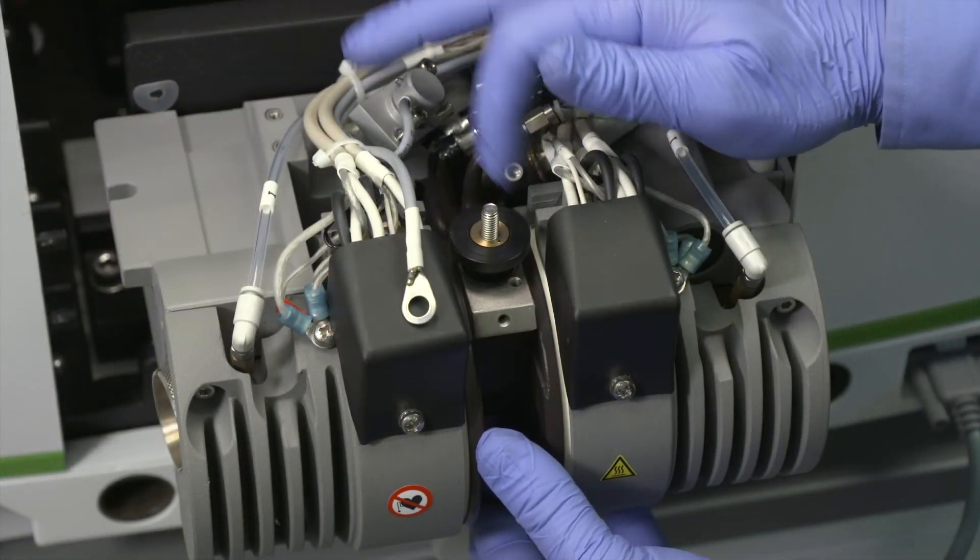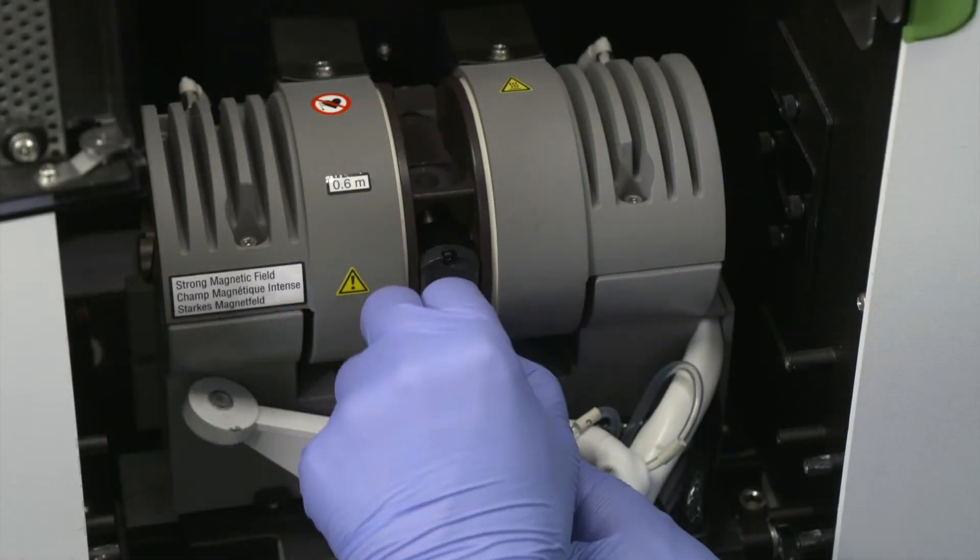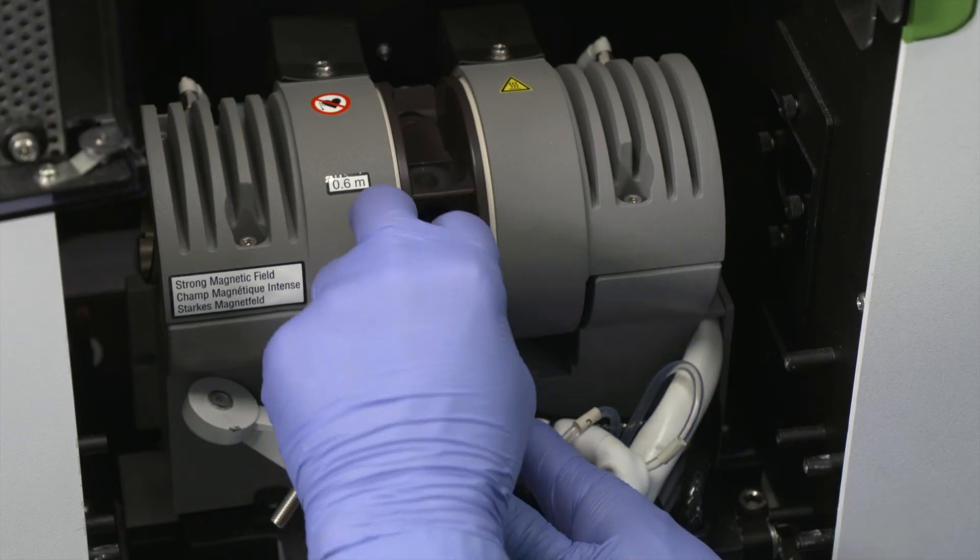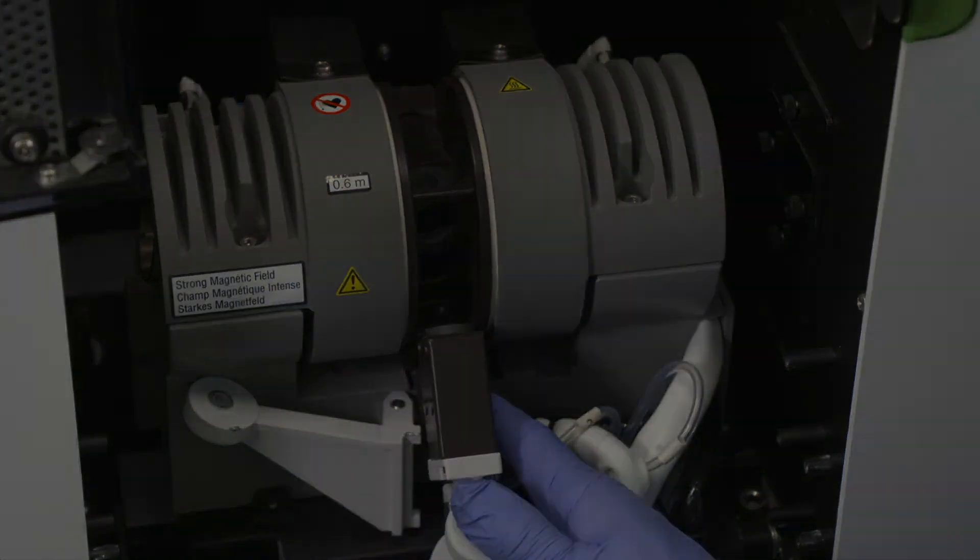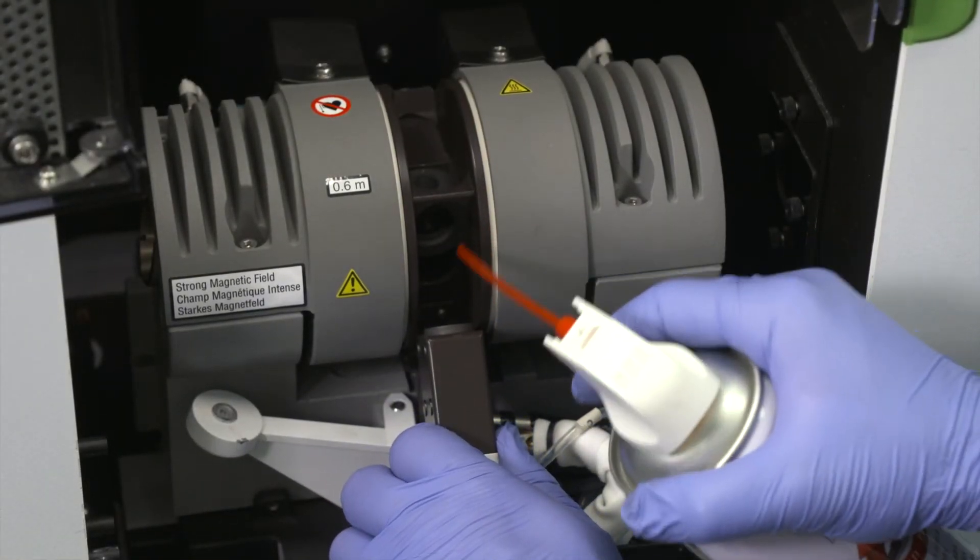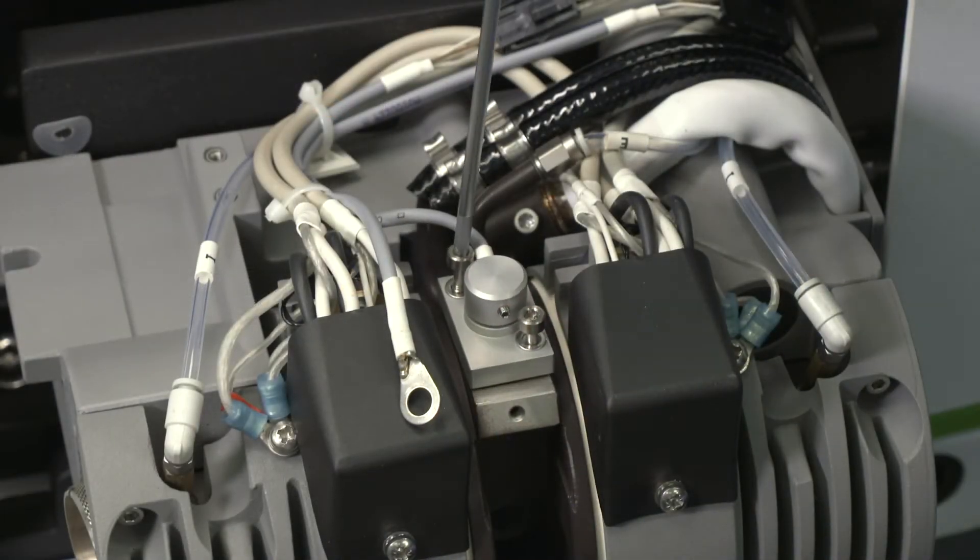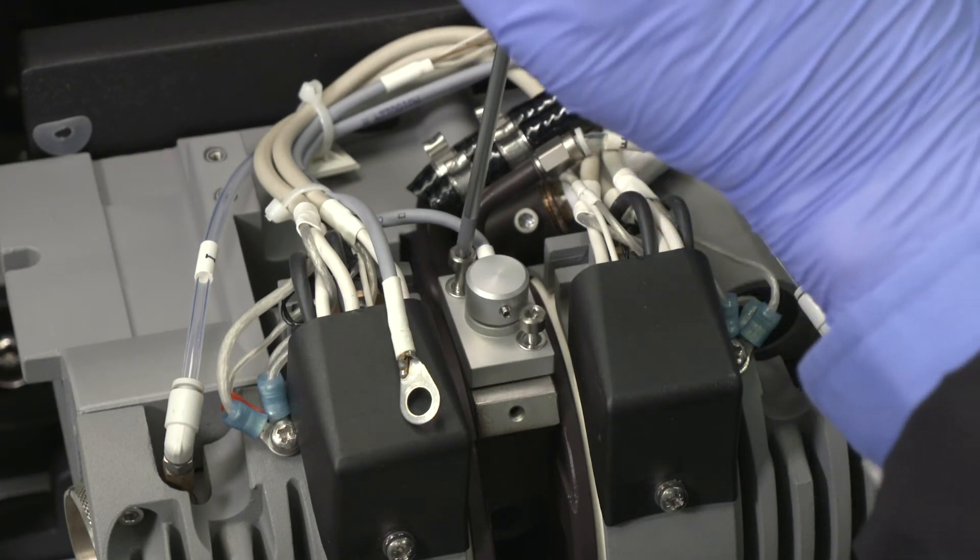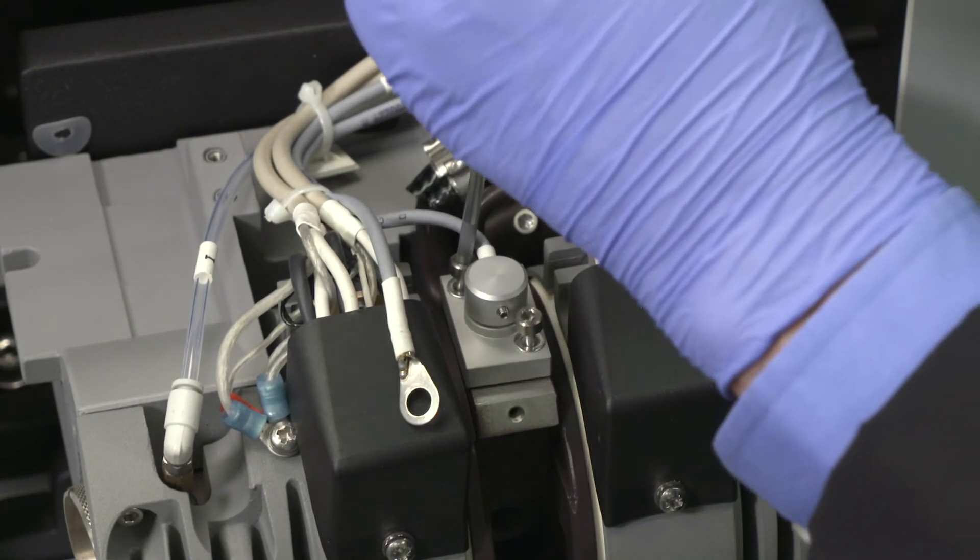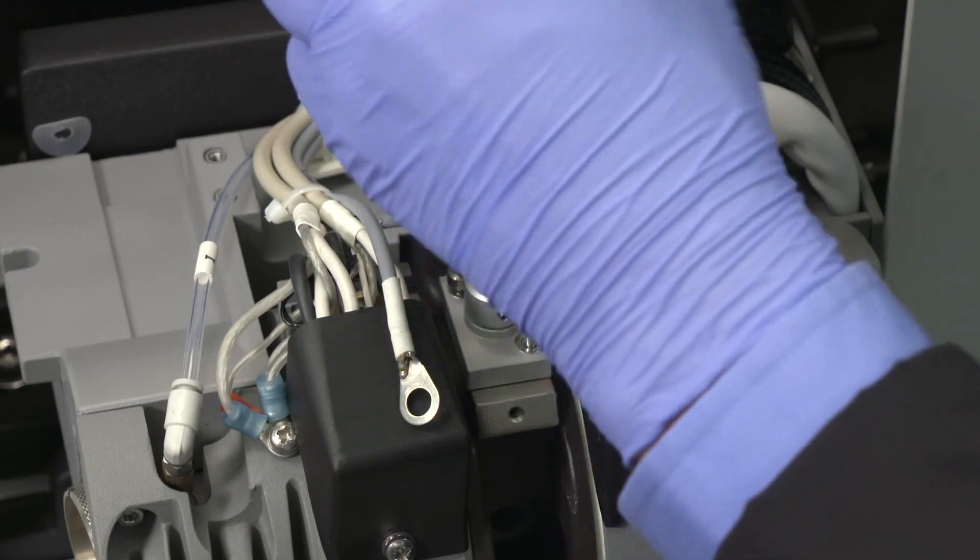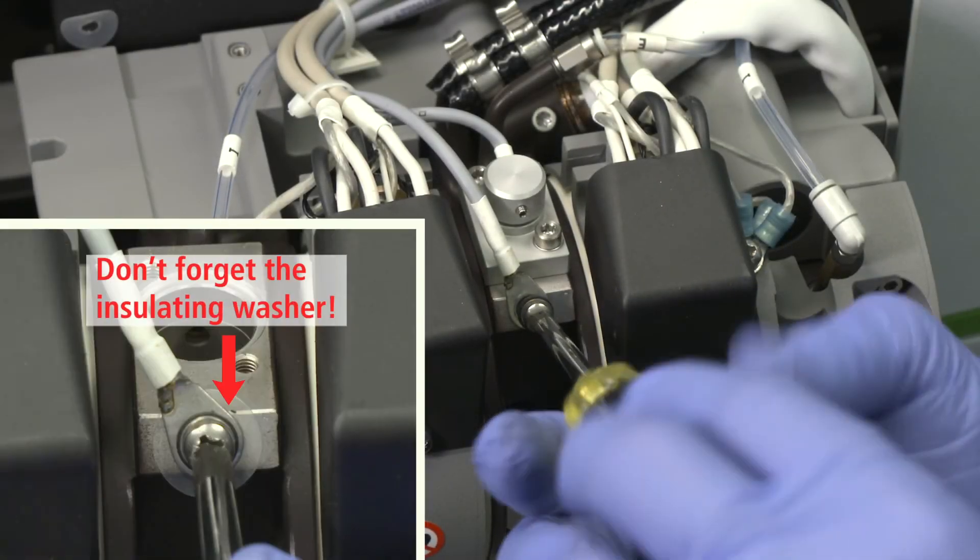Now screw the long bolt out of the threaded cylinder and carefully remove all of the tools. Blow out any graphite particles with compressed air. Push the optical sensor into the rear contact housing. Make sure that you do not damage the O-ring. Tighten the two screws to secure the optical sensor to the rear contact housing and reattach the temperature sensor.